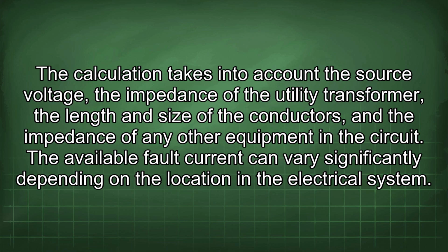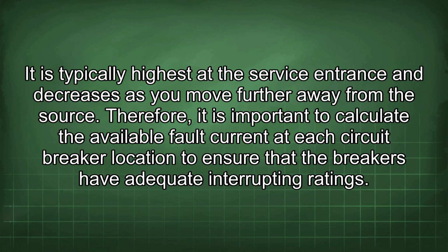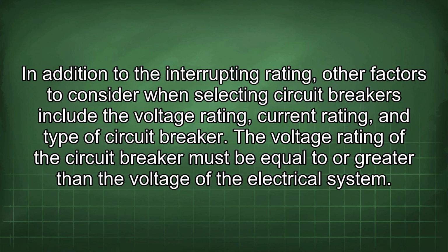The available fault current can vary significantly depending on the location in the electrical system. It is typically highest at the service entrance and decreases as you move further away from the source. Therefore, it is important to calculate the available fault current at each circuit breaker location to ensure that the breakers have adequate interrupting ratings. In addition to the interrupting rating, other factors to consider when selecting circuit breakers include the voltage rating, current rating, and type of circuit breaker.